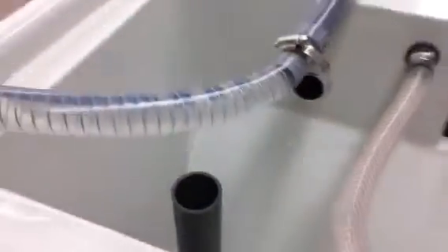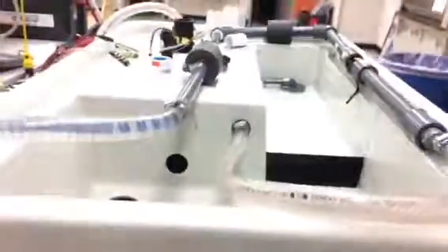And then you might recall we'll drop our valve down here, and that'll make a seal, and we watch the water come up. With stopwatch in hand, it comes up to 0. I don't know if you can see it or not, but you can probably barely see it. Start the watch, and then when it gets up to 15, we'll stop the watch, and we'll have 15 liters in so many seconds. I won't bore you with that.